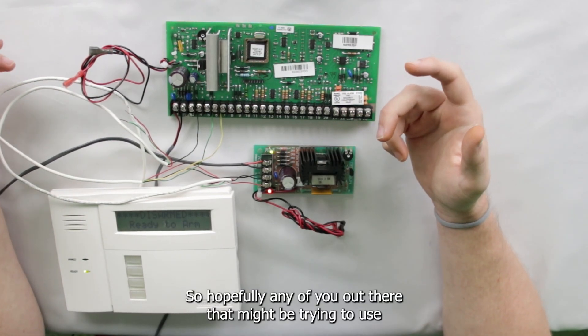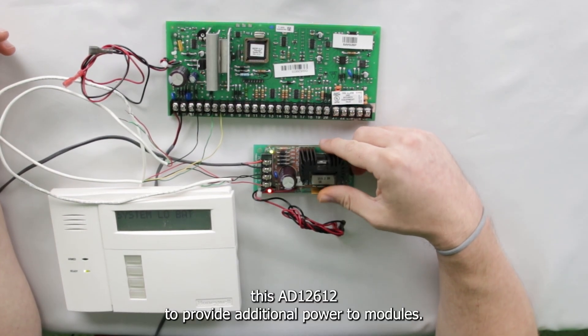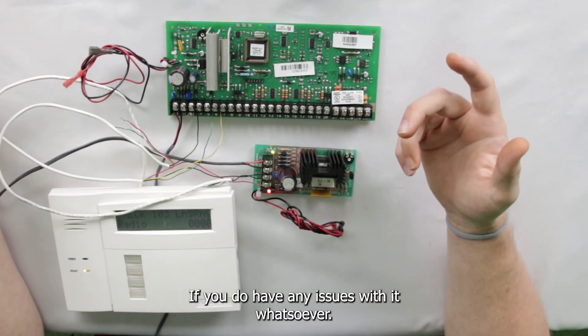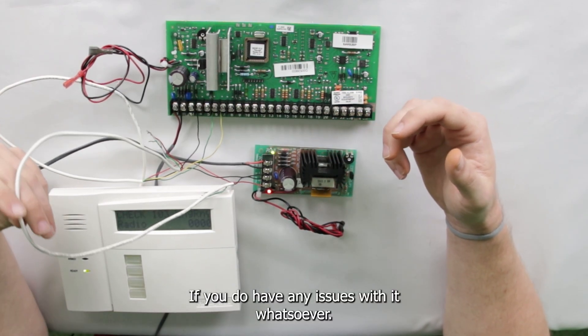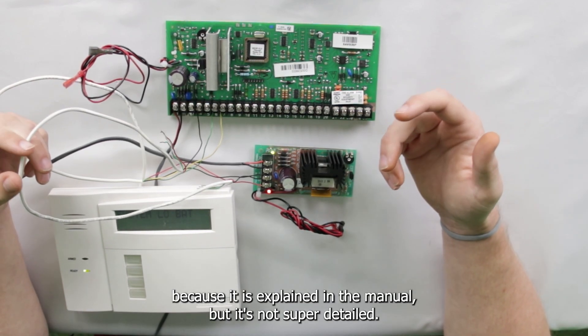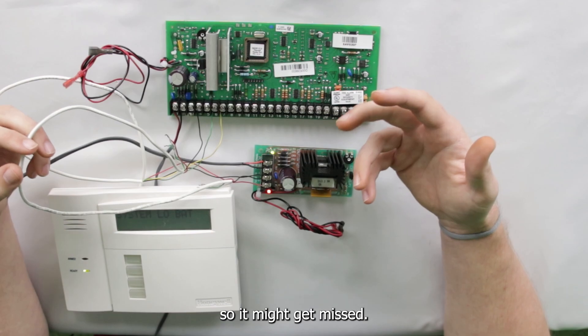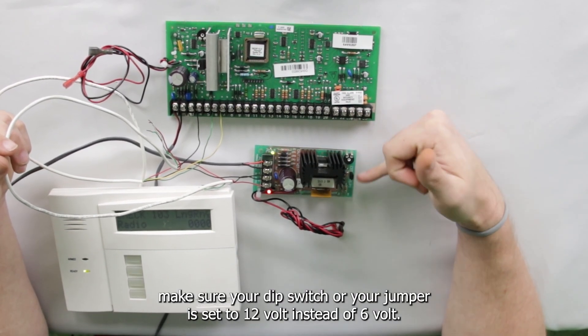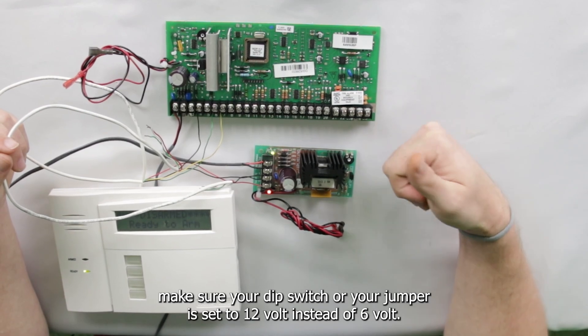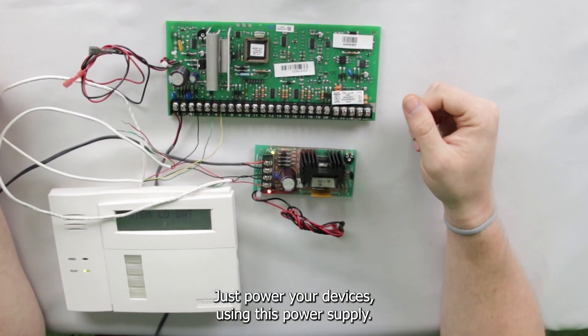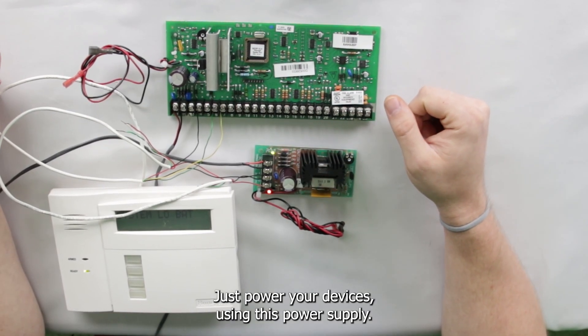So hopefully any of you out there that might be trying to use this AD12612 to provide additional power to modules, if you do have any issues with it whatsoever, nine times out of ten, it's this ground cable because it is explained in the manual, but it's not super detailed, so it might get missed. So make sure you do that. Make sure your dip switch or your jumper is set to 12 volt instead of 6 volt. And it's literally that simple. Just power your devices using this power supply.